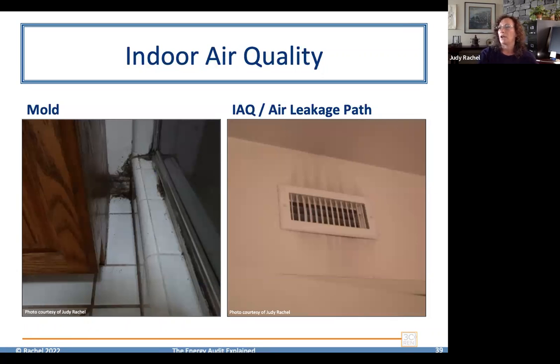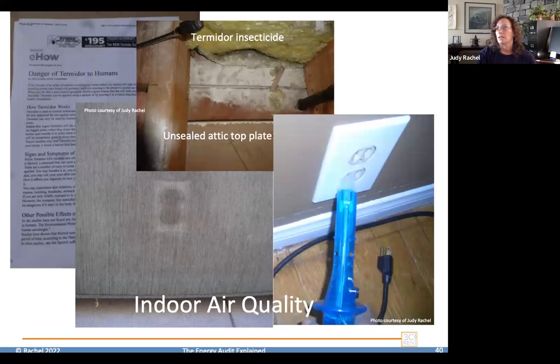Indoor air quality in our homes, just that there was mold growing back here. When you see these signs of what a lot of homeowners feel is dirt and they don't understand why they can't clean it, this is a sign of air leakage through the air distribution system. So it's a clear sign that there's air leakage. The boot that's behind this grill is not sealed to the interior wall finish, and because of pressure differences, the dirty air is coming out and some of that dirt is impinging upon the wall itself. This is one of those things that goes all the way from the attic into the house.